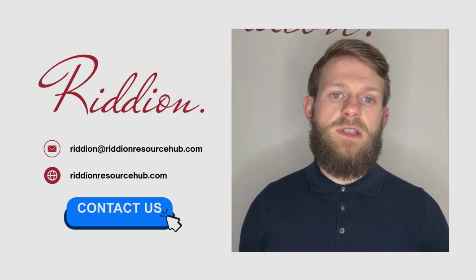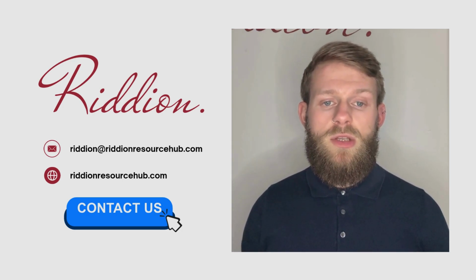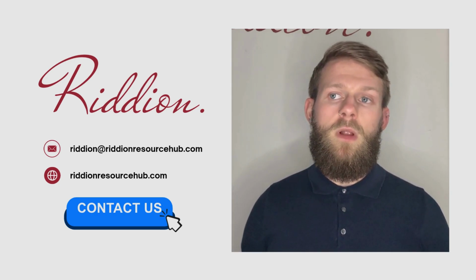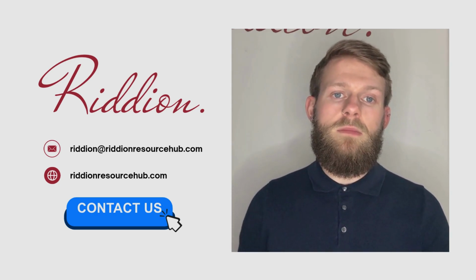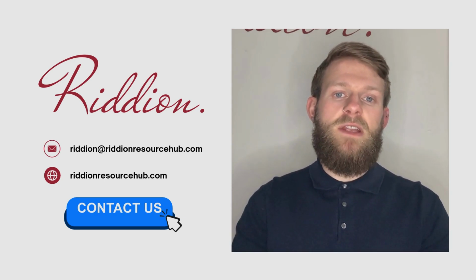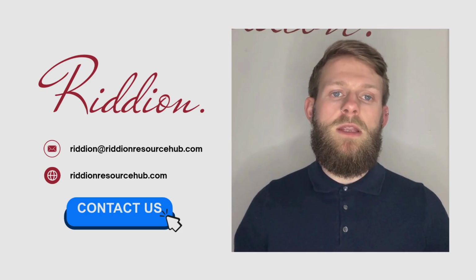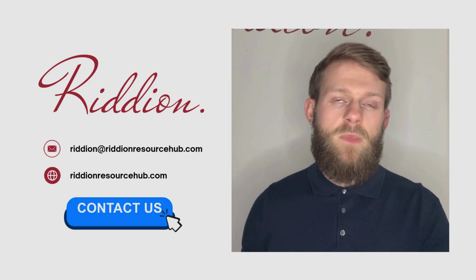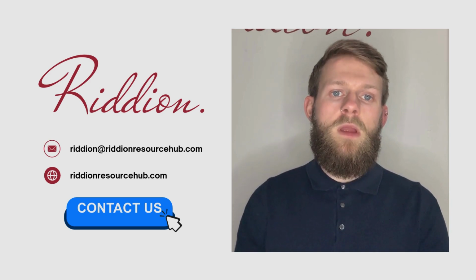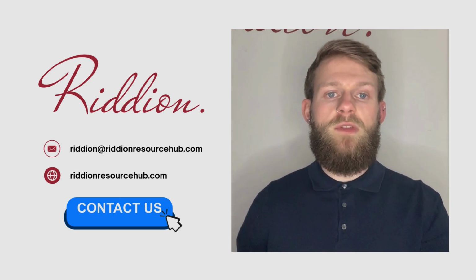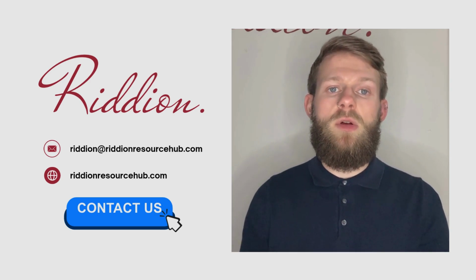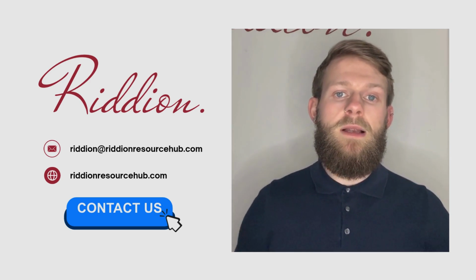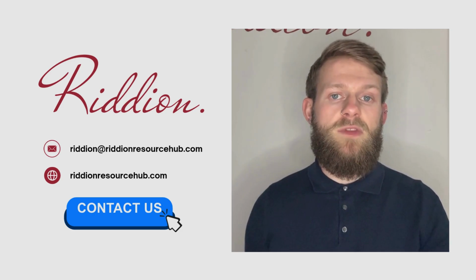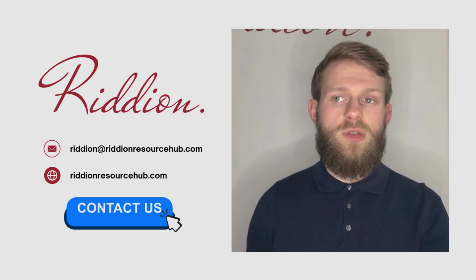One of the biggest differences is the requirement for a basic UDI-DI. Unlike the FDA system, which assigns a device identifier for each version or model, the EU requires an additional identifier, the basic UDI-DI. This identifier doesn't appear on device labels, but is used for regulatory documentation and reporting. Essentially, it acts as a grouping mechanism for related devices within the same regulatory submission.